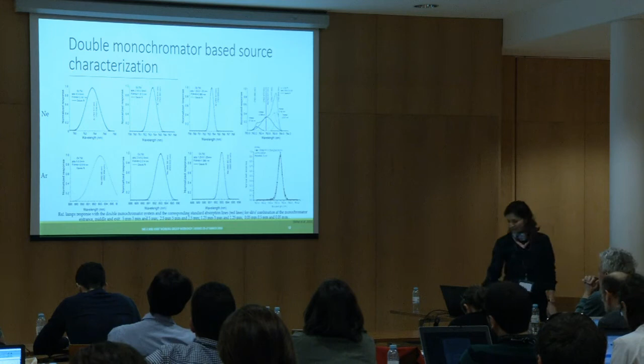I would say that this method is better to be used for spectral calibration, because it's much easier to find out what the correction to be applied should be. And the same thing holds in the case of full width half maximum. Practically you obtain a similar full width half maximum, because this is determined by the system configuration. But you can find the exact spectral resolution of your system, at exactly the wavelength, much more easily. Of course, using a monochromator system is much more time consuming.